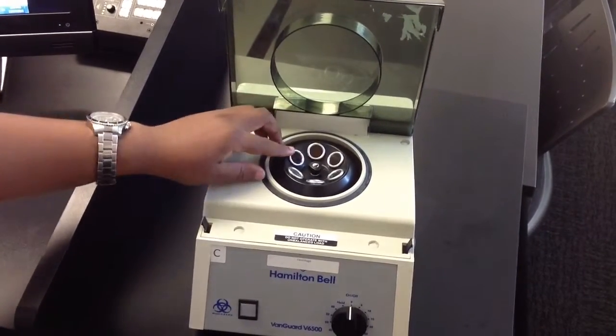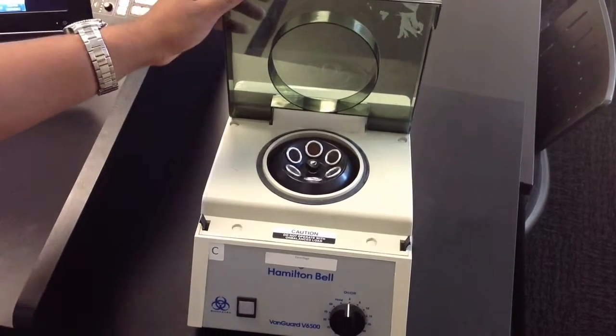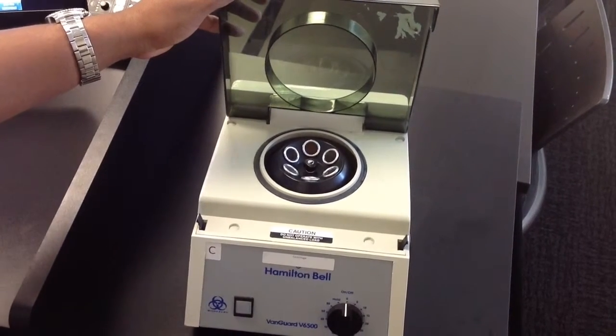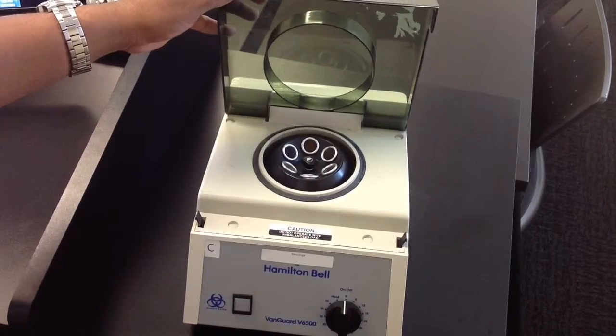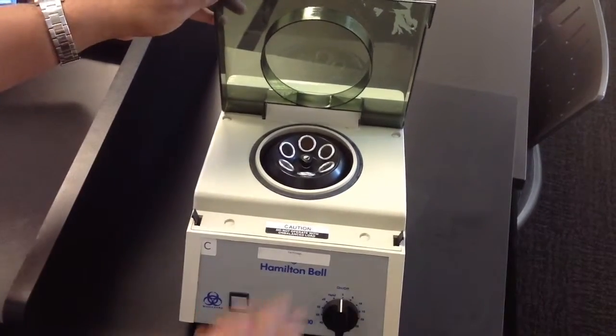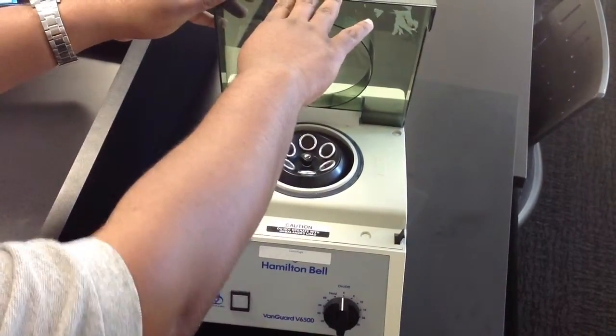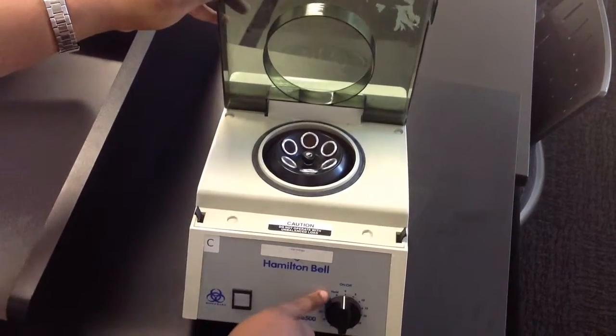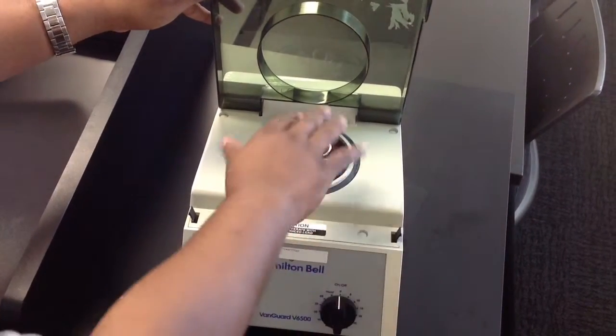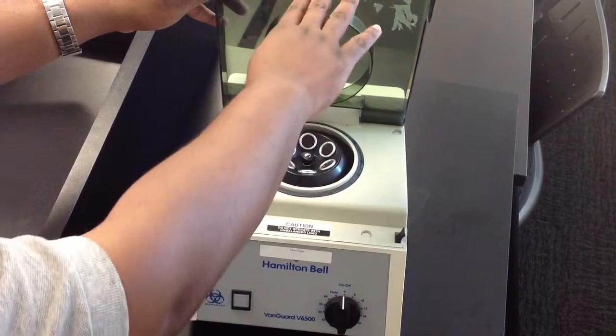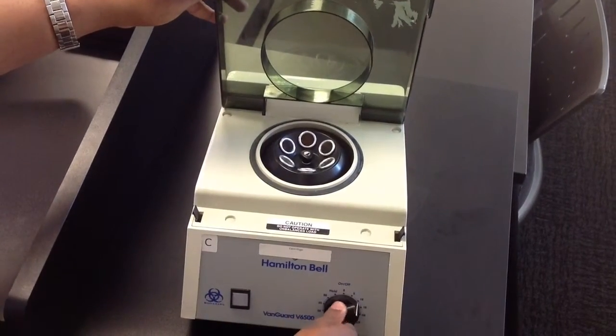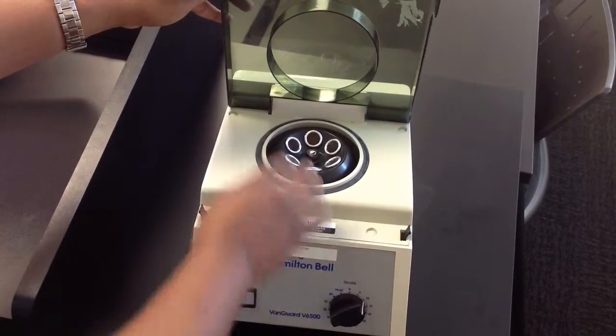same mass. At this time, we're going to go ahead and run the centrifuge and just show how fast it can spin, the speeds. At all times, this lid must be closed. The centrifuge actually has a safety. Here's the timer here. When you turn this timer, normally the rotor starts to spin, but with this lid up, it will not. I'll go ahead and show you. It has a safety. The timer's clicking, but nothing's happening.